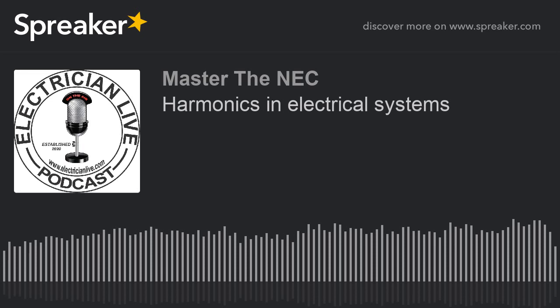Now, how do we solve this when it comes to a transformer? Most people, I would assume, know this, but you can actually buy a transformer that is designed specifically to operate within these harmonic frequencies. It's designed to operate within the third triplen harmonic, and it's typically referred to as a K factor type of transformer that's designed specifically for this function or this condition.